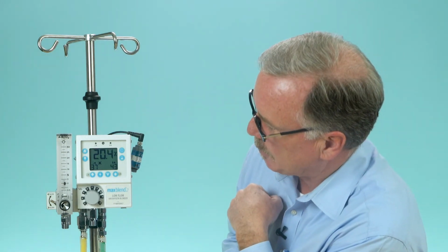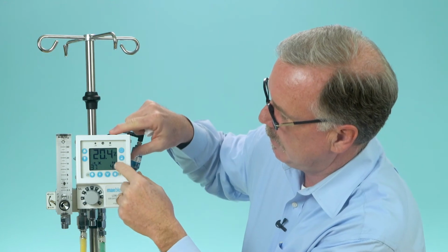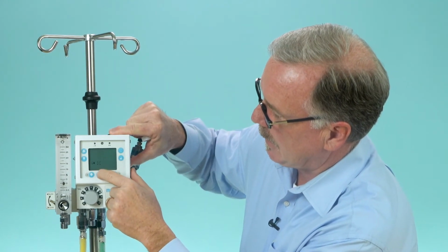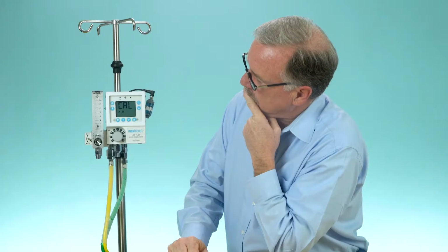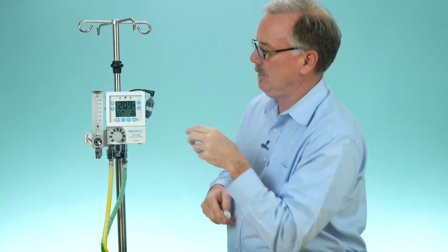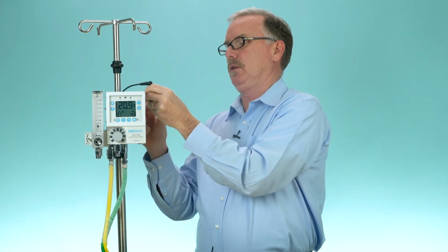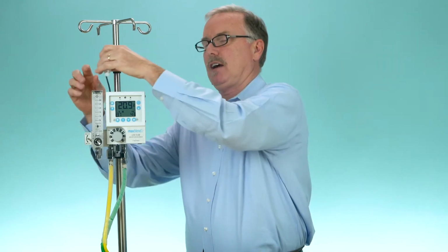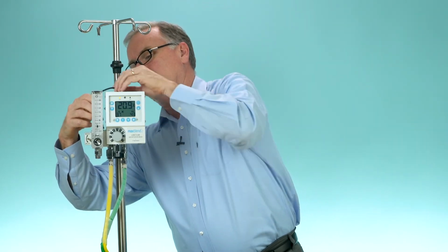So now I could go into the calibration process of unlocking and calibrating. Okay, so now I'm calibrating the room air. As soon as the calibration comes in, I put my diverter back on. And this will also show you and highlight how fast our fuel cells actually are. Put it back into the diverter port. It'll rapidly go to where I had it set. I had the alarm silence on, that's why we didn't hear an alarm breach. And I have now done a 1-point room air calibration without interrupting patient care.